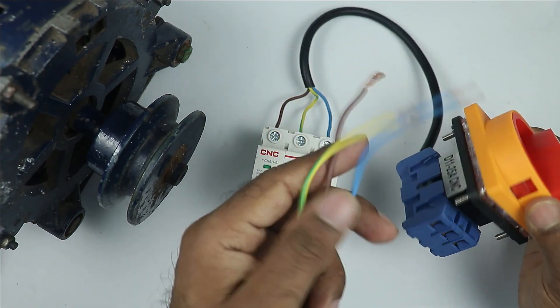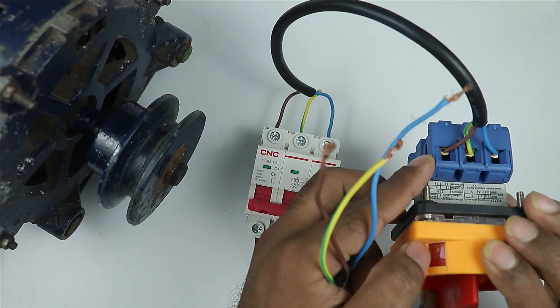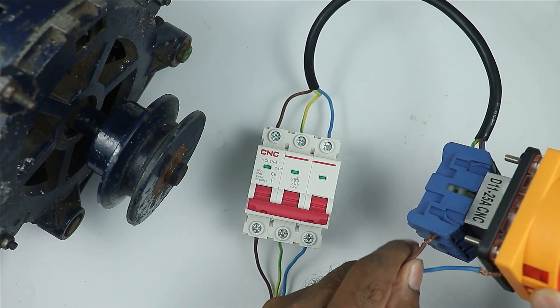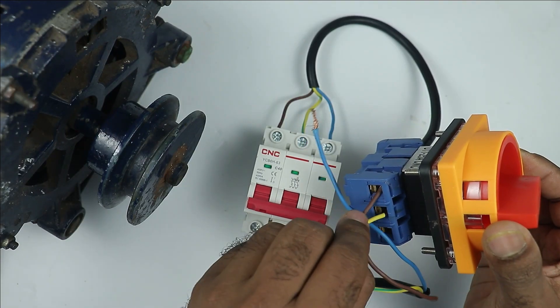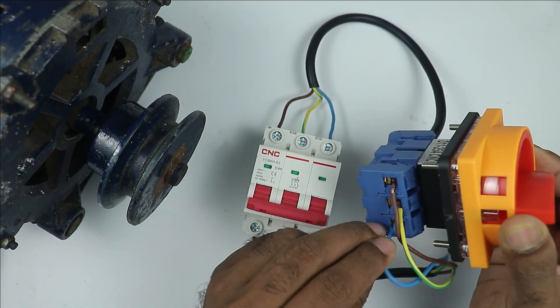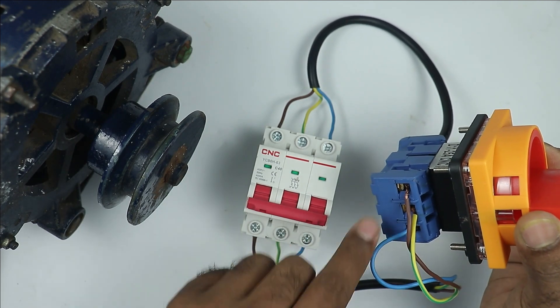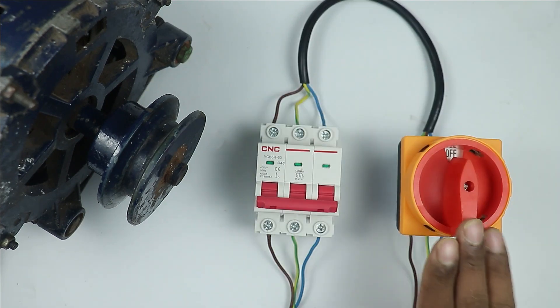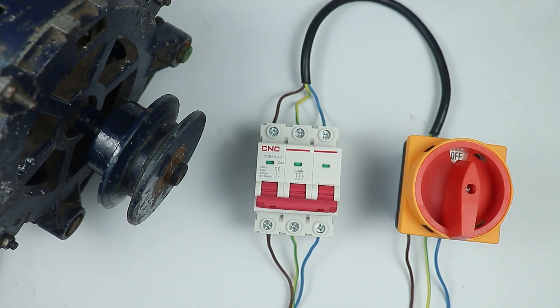When you are connecting, keep phase sequence in mind. On the terminal where R phase is connected, at the output also connect R phase. Similarly at middle, connect Y phase and at last terminal connect B phase wire. So R, Y, B connected in sequence here. So for rotary switch, only this much connection is required.